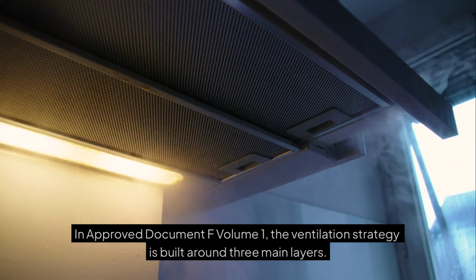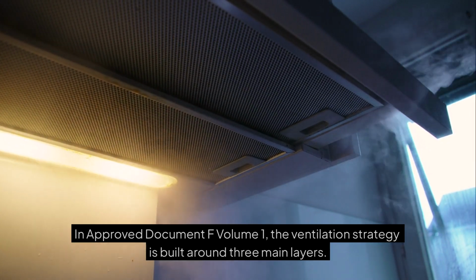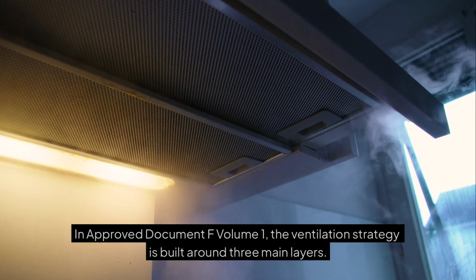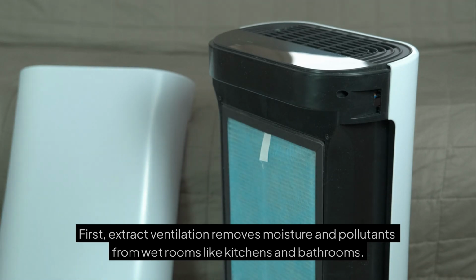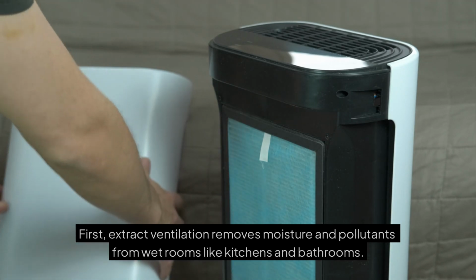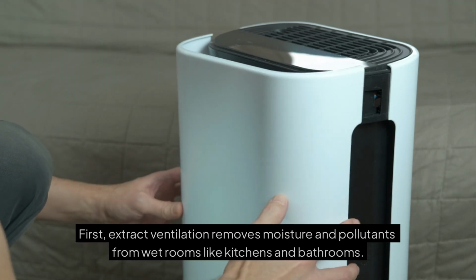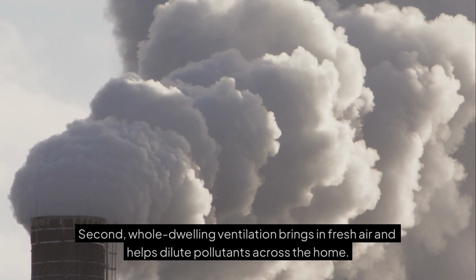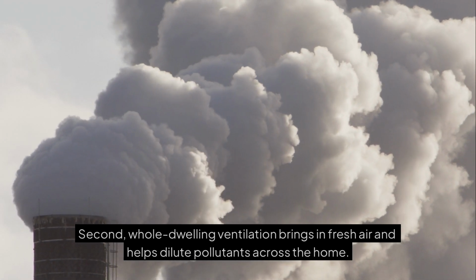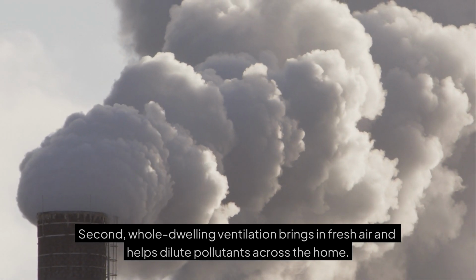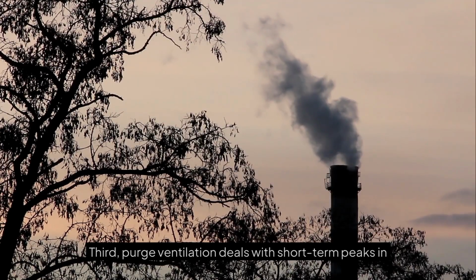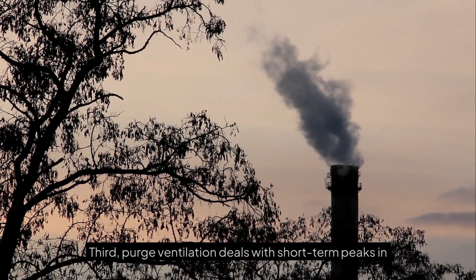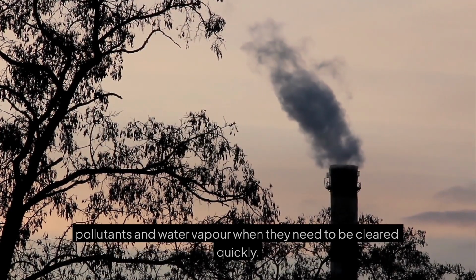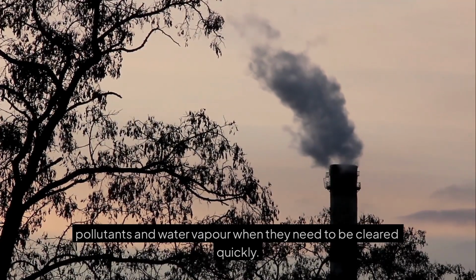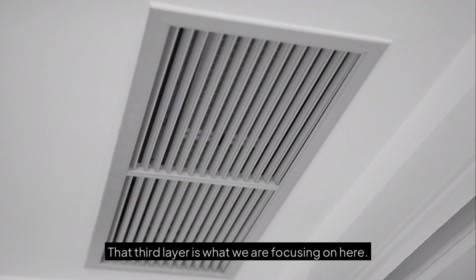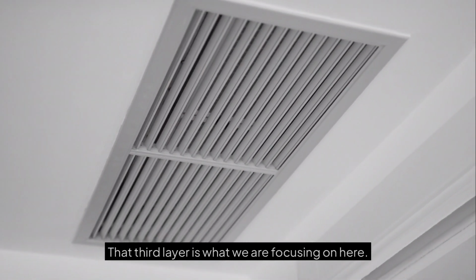In Approved Document F Volume 1, the ventilation strategy is built around 3 main layers. First, extract ventilation removes moisture and pollutants from wet rooms like kitchens and bathrooms. Second, whole dwelling ventilation brings in fresh air and helps dilute pollutants across the home. Third, purge ventilation deals with short-term peaks in pollutants and water vapor when they need to be cleared quickly. That third layer is what we are focusing on here.